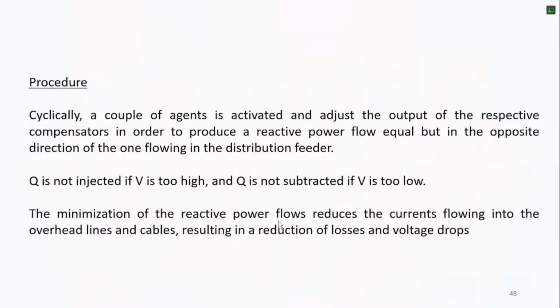And obviously, Q is not injected if the voltage is too high. So if in the bus the voltage is too high, you cannot inject reactive power, because in general we associate injection of reactive power with an increase of the voltage and absorption of reactive power with a decrease of the voltage. And Q is not subtracted, so it is not taken out, if the voltage is already too low.